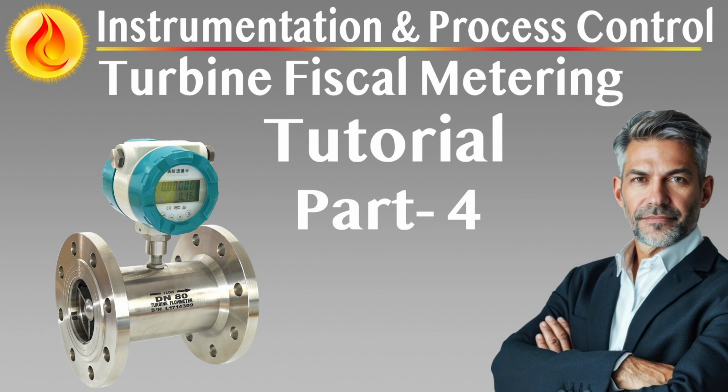Wet functional testing. The fully assembled metering system must be tested with flowing liquid, typically water, to demonstrate complete functionality under realistic flow conditions. This includes proving loop operation, signal verification, flow modulation, sampling system actuation, and system response to varying flow rates. Temporary pumps, tanks, and circulation piping must be used to simulate full-scale operation.